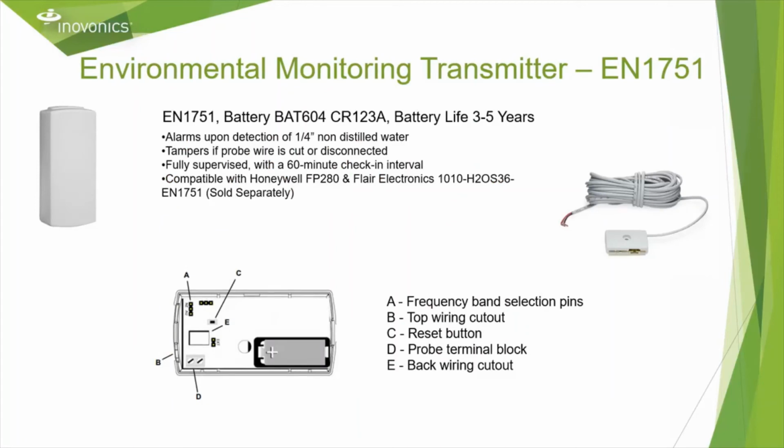The EN1751 has a 3 to 5 year battery life. It alarms upon detection of a 1/4 inch of non-distilled water, will send a tamper message if the probe wire is cut or disconnected, and is compatible with both Honeywell and Flair Electronics probes.